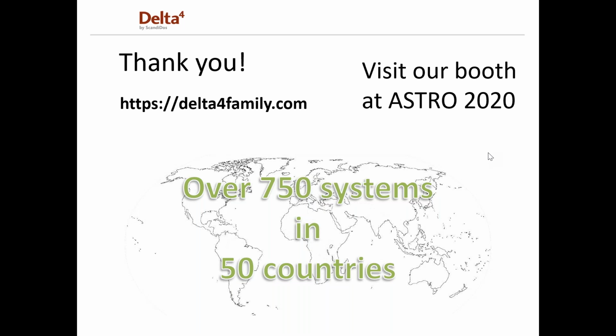We have one here. It says, can the Phantom Plus be used with multiple Linacs within the department? Yes, it can. As I mentioned, it's compatible with Tomo, Halcyon, and those types of Linacs. And what you'll do is purchase various software packages. We have the VMAT package, which is compatible with the Varian machines and the Elekta machines. Then there's a separate software package for Tomo, Halcyon, and you can use the Phantom on any of those machines.